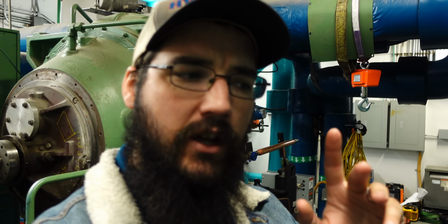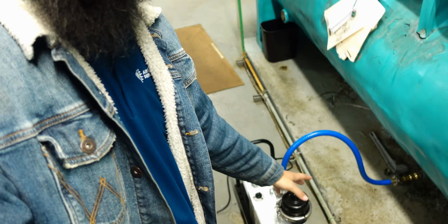One piece of feedback I've gotten on this vacuum pump is that there's one guy in particular who said he wasn't allowed to use this pump in a particular customer's plant anymore because it was so bad about pumping a fog out, filling the plant up with whatever fog. The vapor exhaust port was just outputting a gas regardless. And if I understood his comment correctly, it was even with using the exhaust filter like what I have. I don't know. I'm curious, I'd like to see some more conversation about it, because in my experience, whether I was up on a roof or in an enclosed plant like I'm in now, I've seen no change. I've not seen anything exhaust out of that. Maybe they've come up with a more recent design, or modified some things, I don't know. Either way, that feedback, I just wanted to respond to it. I was sitting here thinking about it and just want to let you know I have not had that experience whatsoever.